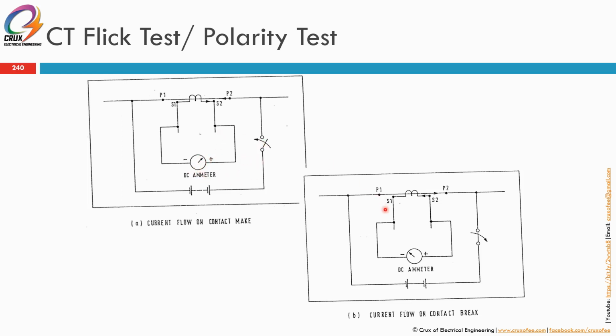If one of the CTs is not pointing in the same direction, it means there could be a problem in terms of connecting, maybe on the secondary side S1, S2, or on the P1, P2 side, which is unlikely. Normally the mistake is on the secondary side. Okay. So this is the flick test, to check the polarity of individual CT. Alright.